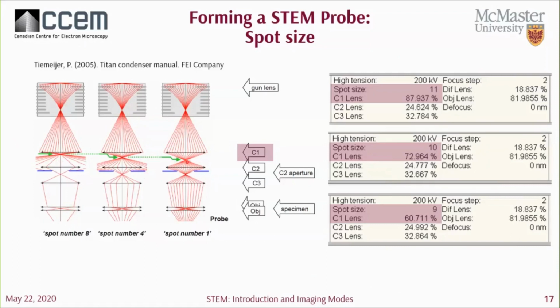So as you increase the strength of the lenses, you're magnifying the image. Sorry, wait. No, you're demagnifying it. Right? Yeah. So we want a really fine probe, so we'll have to go in this direction to increase our spot size in order to further demagnify the source image. In doing so, you'll see that we're increasing the strength of the C1 lens, leading to a greater and greater demagnification of the source.